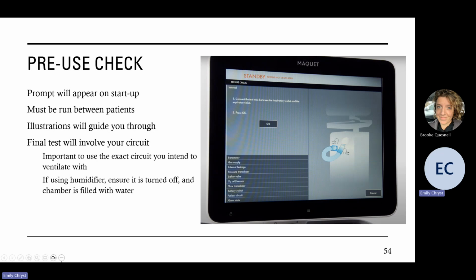So this is going to be testing, not only pressure checking your circuit and making sure that your circuit can actually tolerate what the ventilator needs to do because it's sealed and it's closed, but it's going to be testing the compliance of your circuit. So everything's going to be a little bit stretchy when it's under pressure, right? The ventilator is going to measure that so it can better provide you with patient information that's not lost in the noise of circuit compliance. You definitely have to use the circuit you intend to use for your patient. And if you ever change the circuit for whatever reason, you have to do another circuit test.